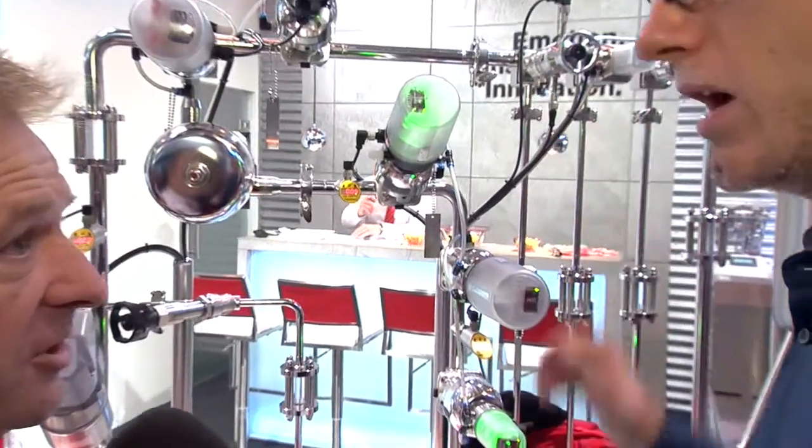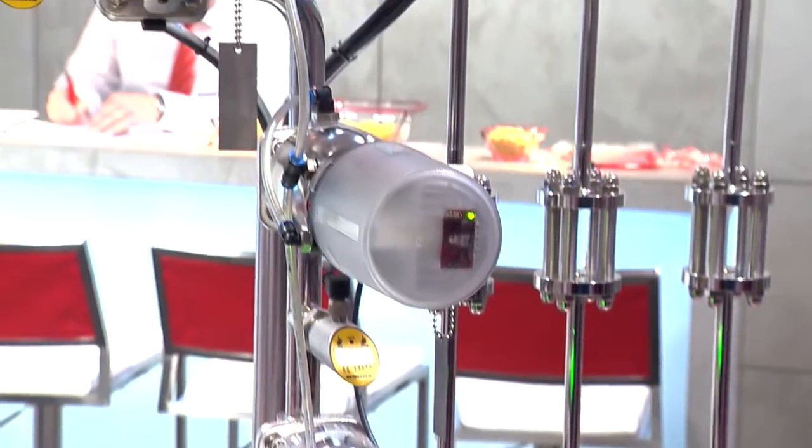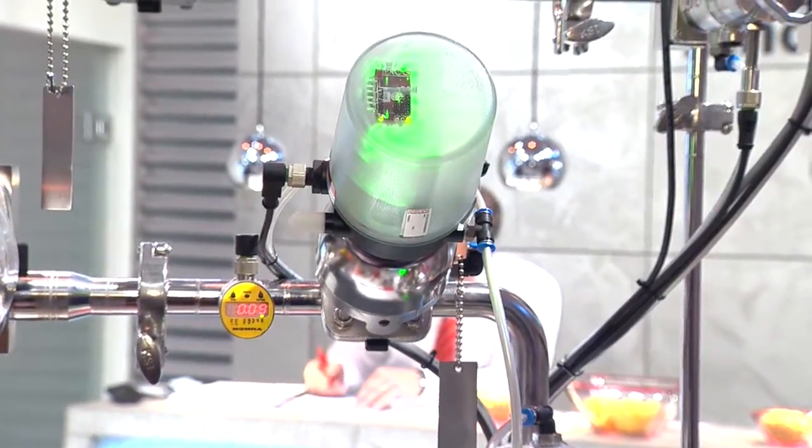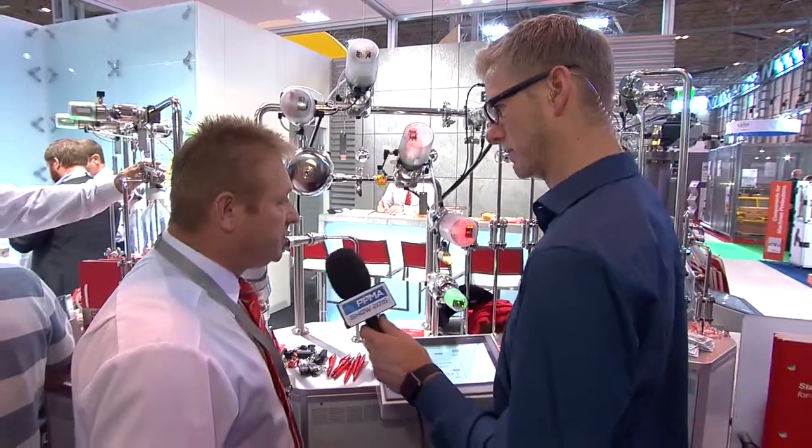Let's take a closer look at some of this, because you've got some flashing lights and some funny noises coming from these. So what you're seeing is valves opening and closing. The great advantage of these is most of you will be able to guess that this is either open or closed. Even better, if that's 40 foot up in the air, you'll still know whether it's open or closed. It's great for the local engineer on site who has a problem — he can go straight to the valve that has a problem because it'll flash a different code. This is not gimmicky; as well as having local indication, you'll also have feedback back to a DCS or a PLC.